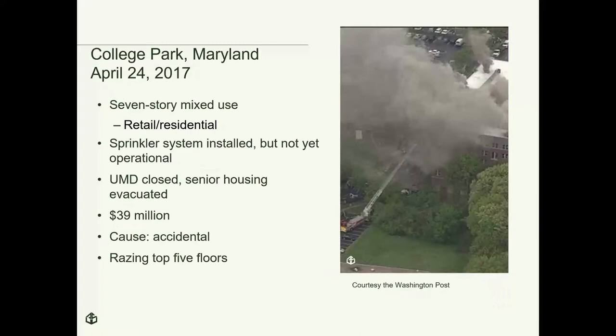The next fire was in College Park, Maryland. This actually shut down the University of Maryland College Park. Debris was in a shaft space, and they think somebody dropped a cigarette in the shaft space and caught the debris on fire. The takeaway was the sprinkler system was installed but not yet operational, and the standpipe system wasn't operational either. The fire department didn't know it, so they hooked up to it and were pumping, but it wasn't conveying water upstairs, so they wasted a lot of time unnecessarily. It burned the roof off the place - that was a total loss.